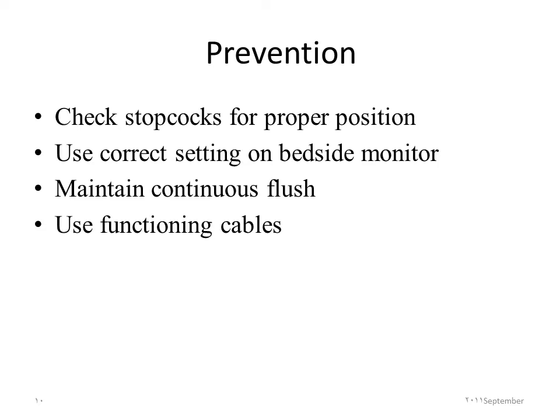How can we prevent these errors? Check the stopcock for a proper position. Use the correct setting on the bedside monitor. Maintain a continuous flush and use functioning and correct cables. The cable is not necessarily wrong; it may be damaged or out of order. These are the 4 steps that could be used to solve the previous problems that appeared in the previous slides.